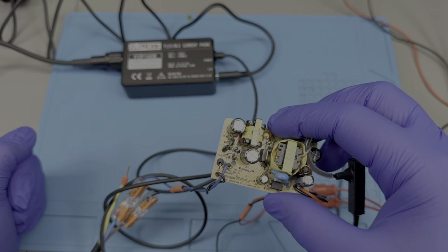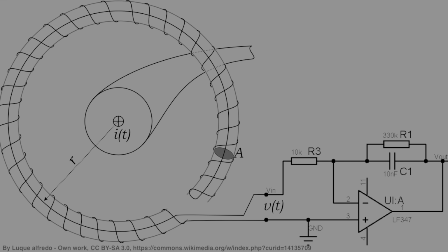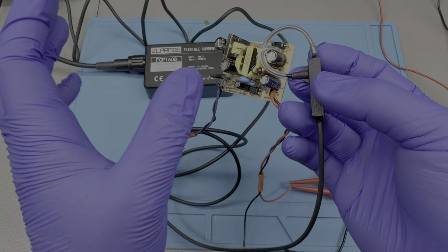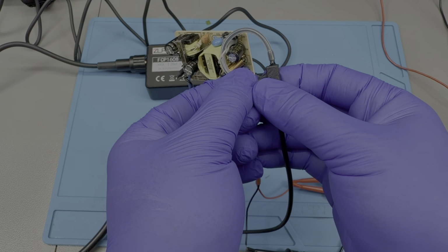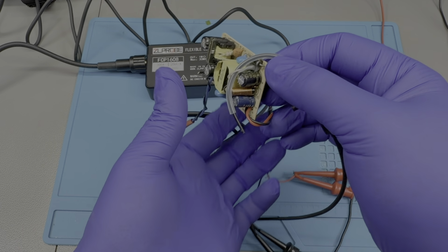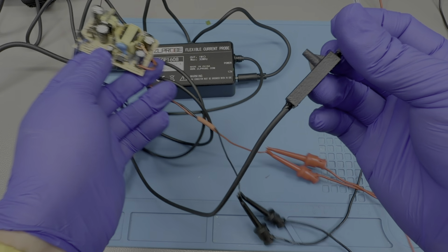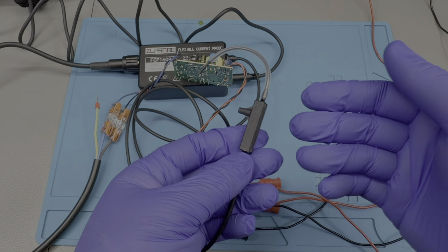But what is a Rogowski current probe? Well, unlike standard current clamps that use a heavy magnetic iron core, a Rogowski probe is just a helical coil of wire wrapped around a flexible plastic core, literally an air core transformer. An AC current passing through the loop will induce a voltage in the coil proportional to the rate of change of current. Now, because of this construction method, one end of the loop can be unclipped from this plastic holder to be wrapped around the point of measurement.